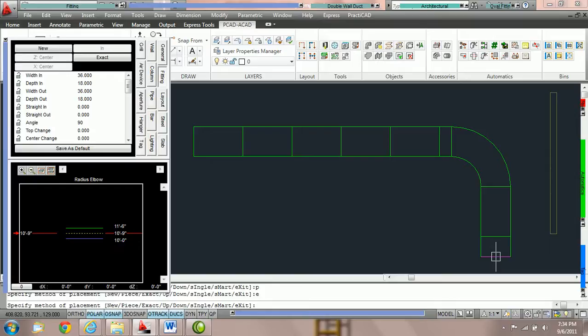Notice that Practicad has not extended the straights of this elbow. What it's doing is it's putting a variable length piece of duct right before the elbow. Exact uses full length pieces of duct and variable length pieces of duct to cover specific distances.